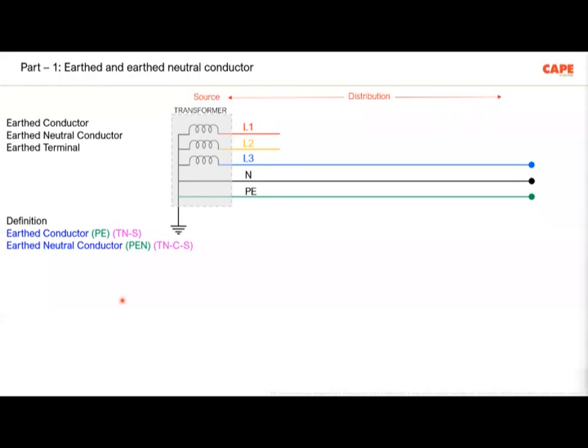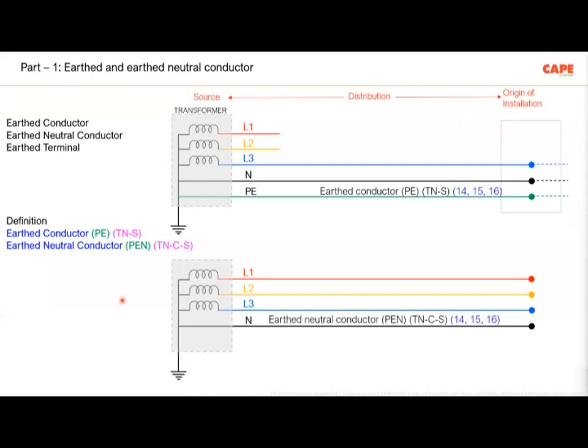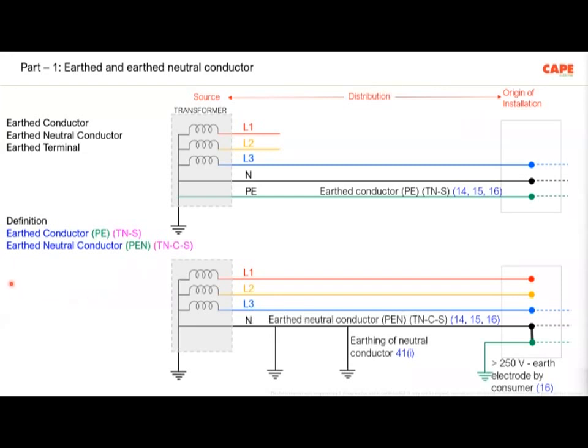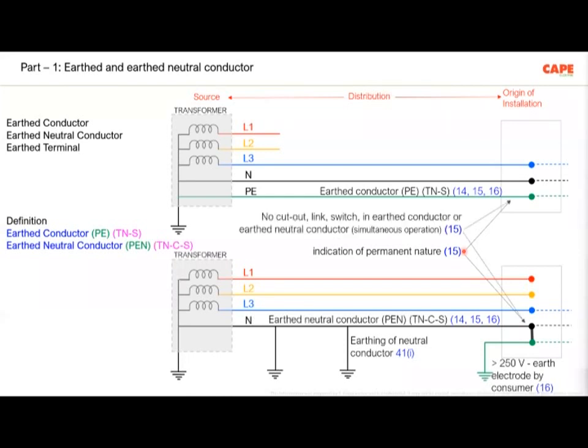This part I covered in my first part, 2 weeks back, but I show it again for people who are new in this program. For low voltage supply, we are supposed to get a TN-S or a TN-C-S supply from the electricity supply company. Regulation 14, 15, 16 of the Central Electricity Authority safety regulation says the power supply company is supposed to give an earthed conductor, meaning a TN-S system, or an earthed neutral conductor to the consumer. Then they say this particular conductor, earthed neutral or earthed conductor, shall have an indication of permanent nature, and no cutout or link shall be inserted in this line.